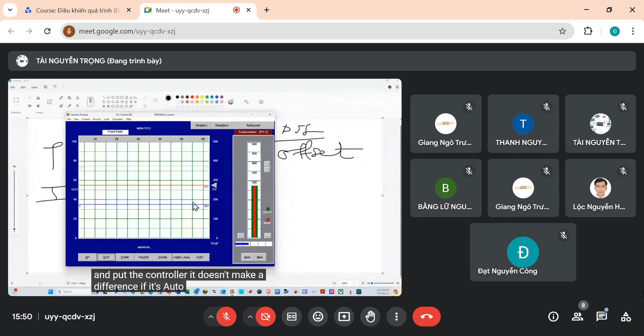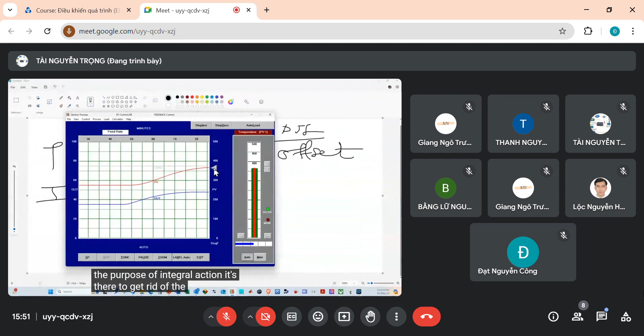Now, if the controller is in automatic and I change the setting, what happens is that my output keeps on changing until I get to the setting. So that's the purpose of integral action - it's there to get rid of the offset. Look at that, I've now managed to get to the setting.